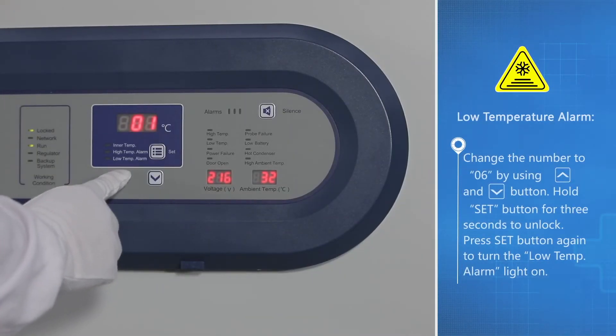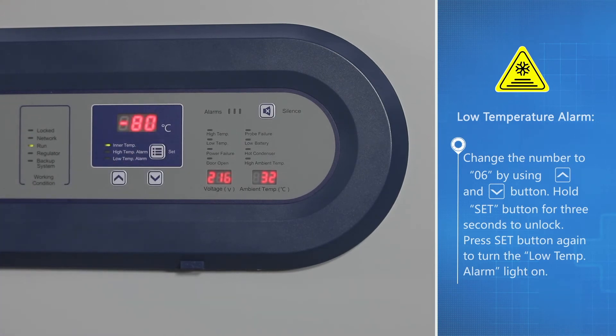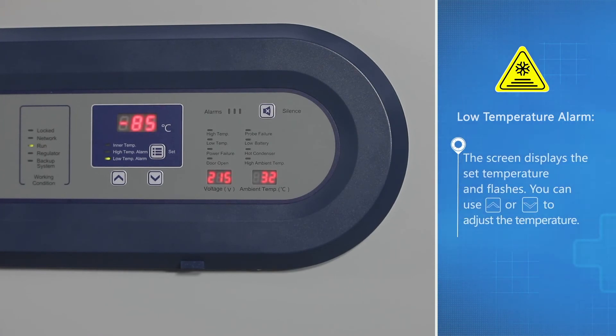Low-temperature alarm: change the number to 06 by using the up button and down button. Hold the set button for three seconds to unlock. Press the set button again to turn the low temp alarm light on; the screen displays the set temperature and flashes.